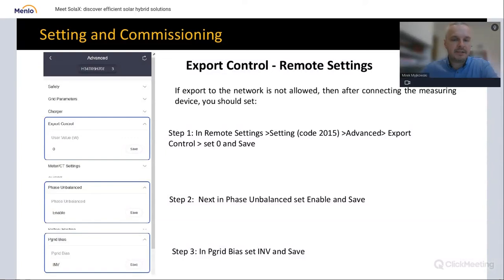The Pgrid bias is just a tendency on the meter. So if you set it to inverter, that means the inverter will keep the tendency of rather taking a little bit from the grid than exporting a little bit to the grid. It's just a tendency, like sliding on carving skis — you cannot go straight, you have to choose which edge you're using. So this is the tendency on the edge, on the meter.